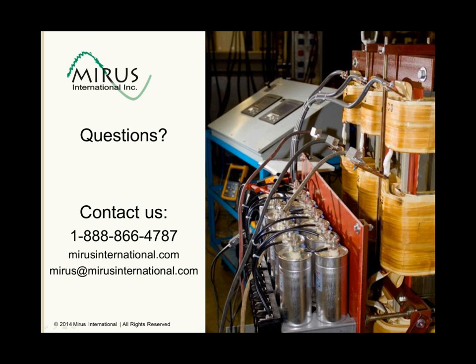And through modeling, we have simulation software that provides modeling of applications for variable speed drives with or without filtering. We simulated an overvoltage ringing condition by adding power factor correction capacitors and introducing a resonance condition, and we found that downstream of the filter, even though we have this ringing and overvoltage on the upstream side, it was substantially reduced. Armed with that knowledge, we applied it on the drilling rig, and I've had many successful applications since then, using it not only to reduce the harmonics introduced by the load it's connected to, but also to protect that load, and more importantly, to protect that load from the distortion on the bus due to other connected loads.